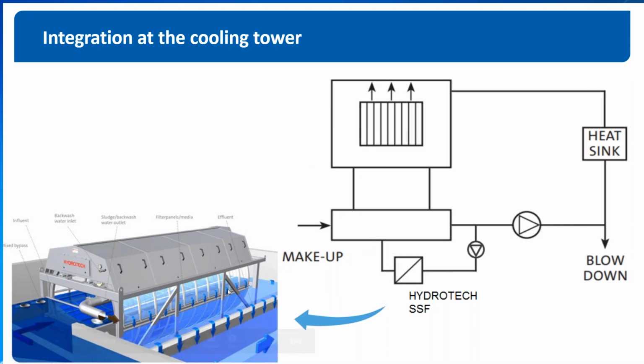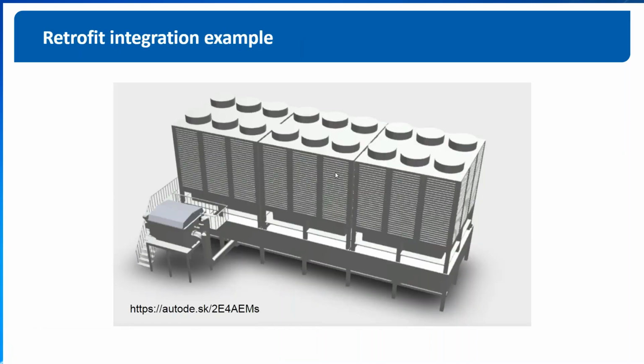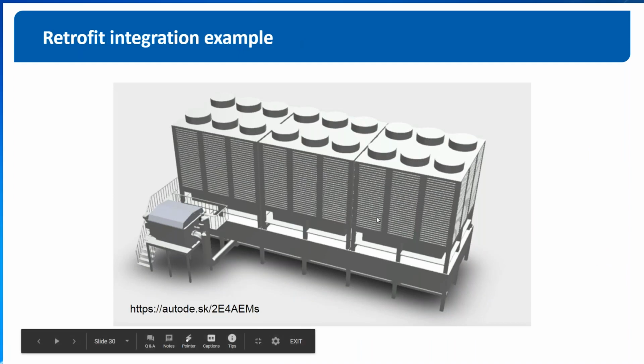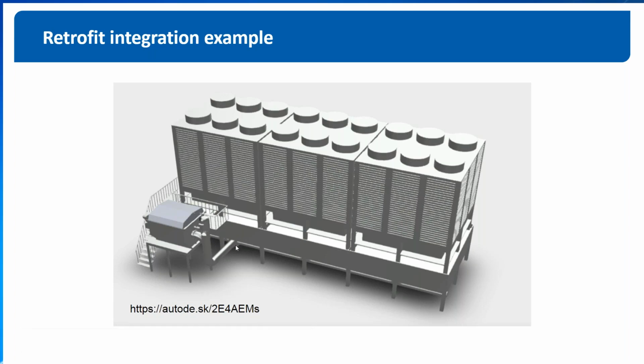Depending on the configuration of the cooling tower, this could be inside a concrete basin. Alternatively, it could be an installation where you retrofit a tank. In the image you're looking at here, we have tapped a pipe into the balancing pipe, which sits below the basins of these three cells. We draw the water up using a propeller pump, pass it through the disc filter, and then it drains by gravity back into the basin of the cooling tower.